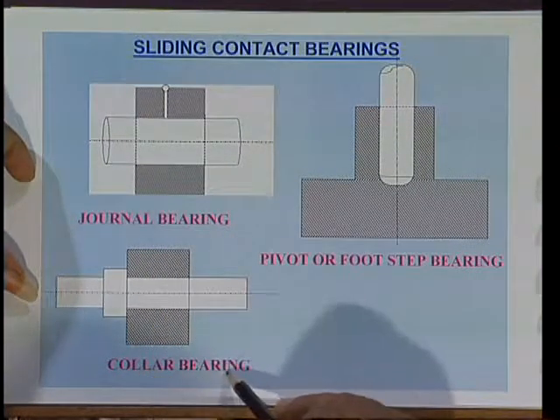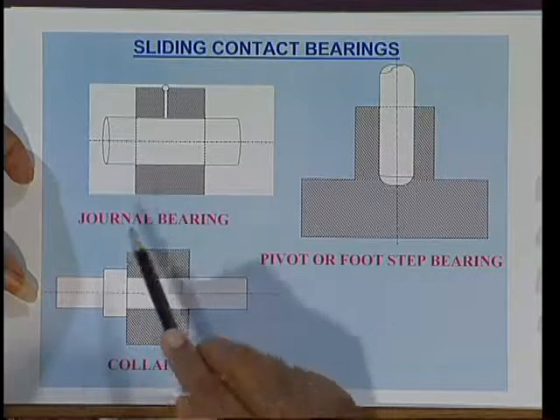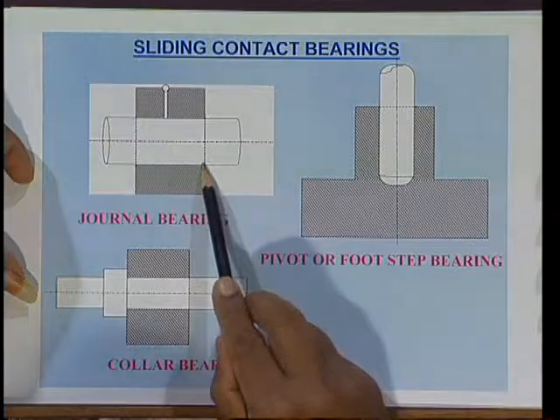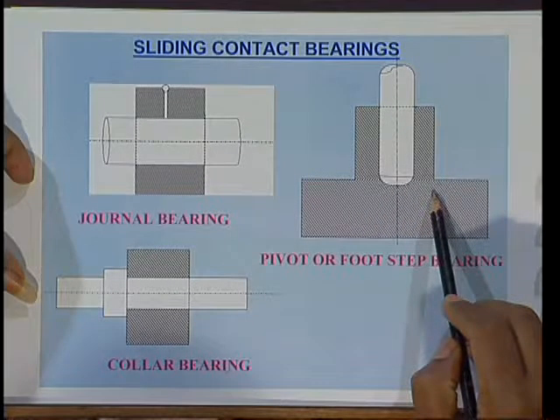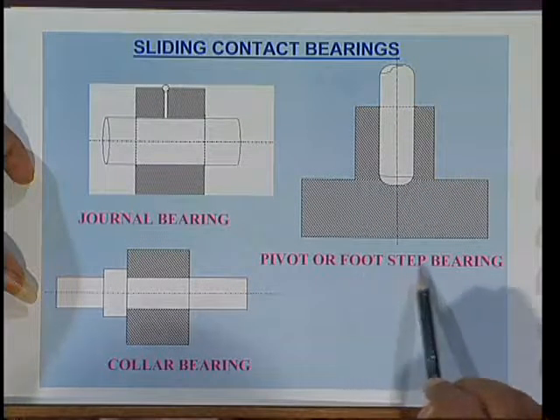Here you can see a collar bearing having only one collar, and a journal bearing which supports the load in the radial direction. Here is a shaft that is vertical and ends in the bearing itself — that is a pivot or footstep bearing. These sliding contact bearings are generally used for higher ratings. The noise compared to ball bearings is very less, but the friction is somewhat more compared to ball or roller bearings. These are the second type of mechanical features of motors.